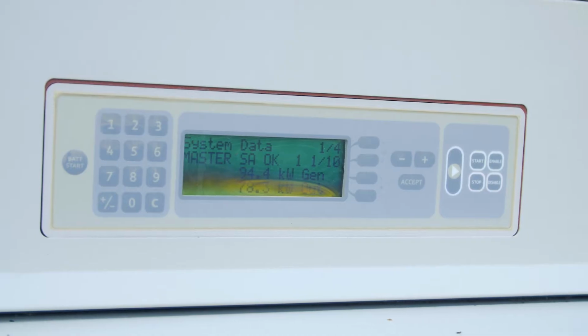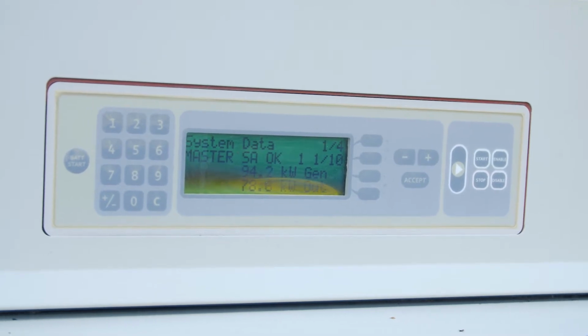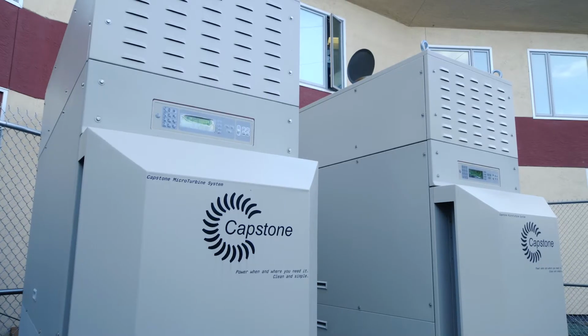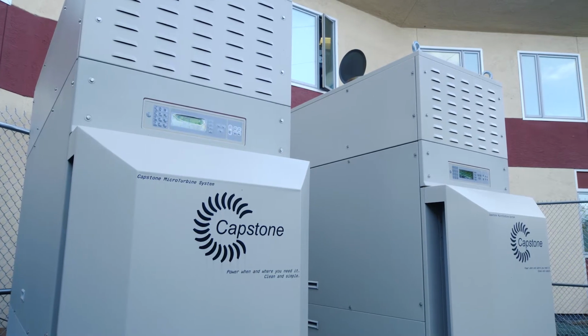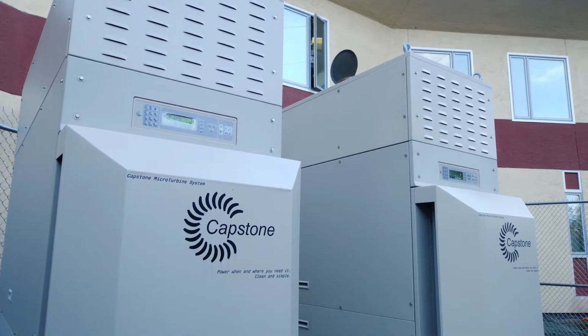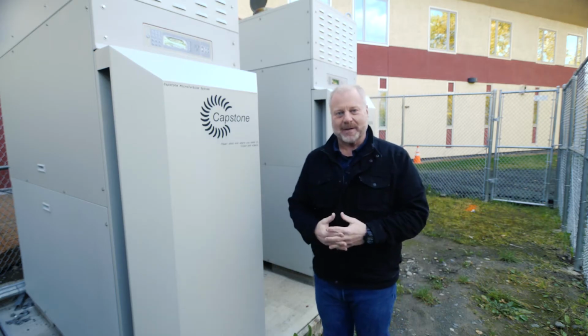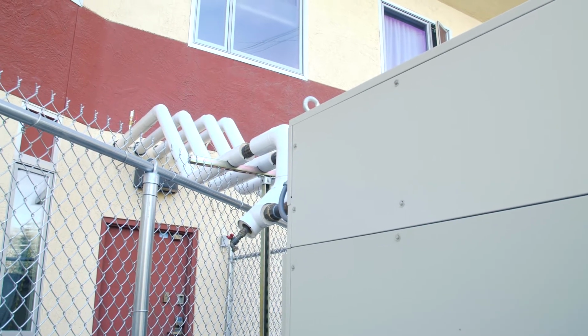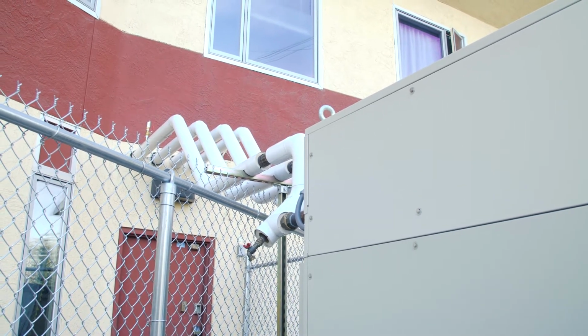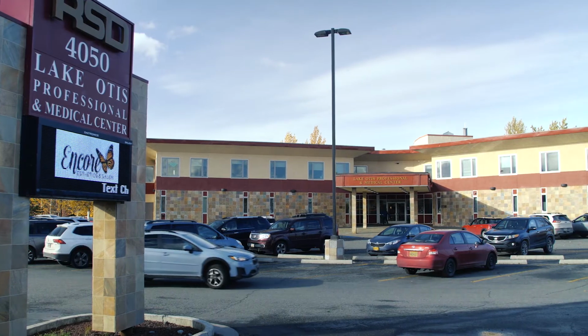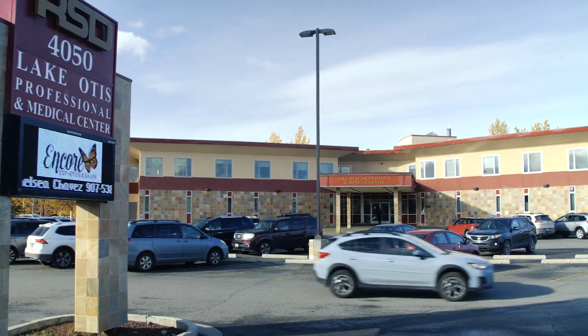This particular array produces 130 kilowatts of electrical power and almost 900,000 BTUs per hour of hot water. The hot water produced by these two turbines flows into the building into an isolated loop and their own heat exchanger, which is set up as the primary boiler in this building.